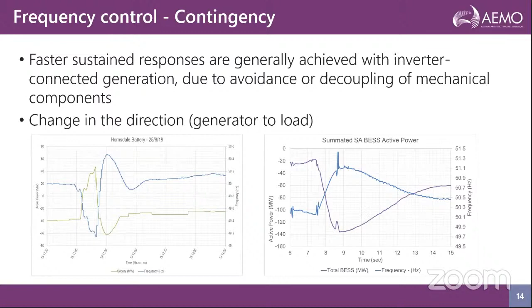And the figure on the right is the response from all three batteries of South Australia to an over frequency event that occurred in 2019. And what we can observe here, the change in the frequency was about 0.9 hertz. The frequency is the blue one. And the change in the megawatt is about 120 megawatt. So when you do a high level calculation, it would come out to be 1.7% droop on 150 megawatt of installed capacity. And it largely matches with how it was configured to operate.